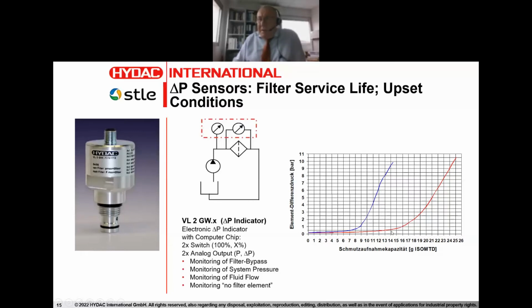Another thing is that this flat line here is indicative of the fact that the depth of the filter is being employed for particle deposition and particle holding, whereas the straight line indicates that the surface active mechanism is operative. So what we have here is cake, the caking effect. What we can distinguish between these two situations is that if the system is subject to a high level of hydrolysis and gel formation, or varnish or whatever, even though I hate that word, because varnish doesn't really mean anything in turbine lube oils. Varnish is a different animal compared to paper lubricating oils, but people still call it varnish. Basically, with soft gelatinous materials, the caking effect is operative, and therefore the filter service life is much shorter, and what we see is this straight line behavior. In a normal operation, where the particulate is loading the depth of the filter first, we would see this flat line running for a long, long time.